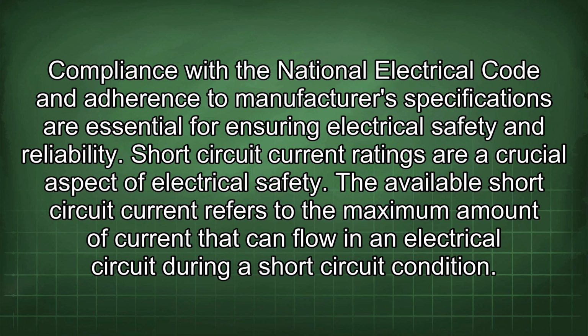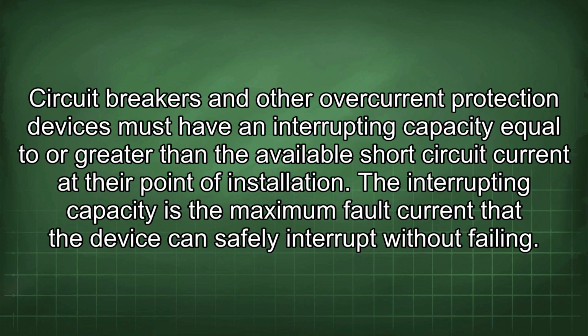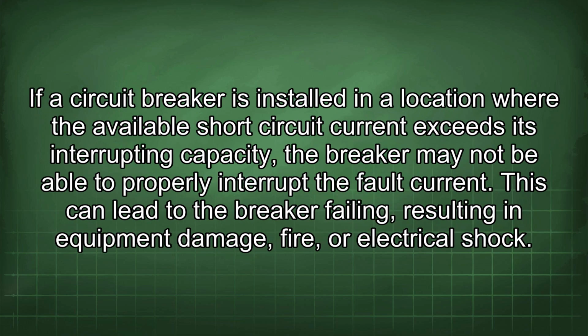Short-circuit current ratings are a crucial aspect of electrical safety. The available short-circuit current refers to the maximum amount of current that can flow in an electrical circuit during a short-circuit condition. Circuit breakers and other overcurrent protection devices must have an interrupting capacity equal to or greater than the available short-circuit current at their point of installation. The interrupting capacity is the maximum fault current that the device can safely interrupt without failing. If a circuit breaker is installed in a location where the available short-circuit current exceeds its interrupting capacity, the breaker may not be able to properly interrupt the fault current. This can lead to the breaker failing, resulting in equipment damage, fire, or electrical shock.